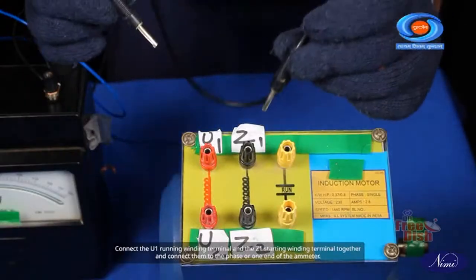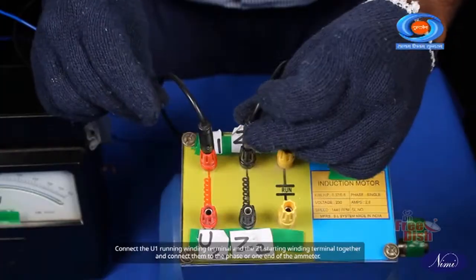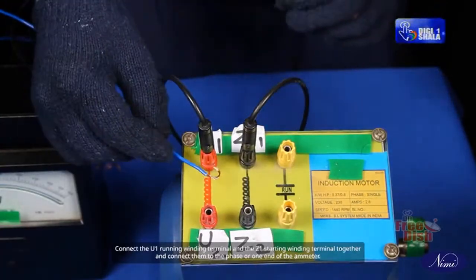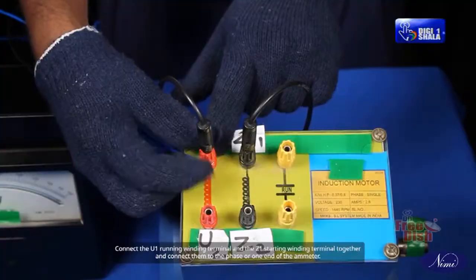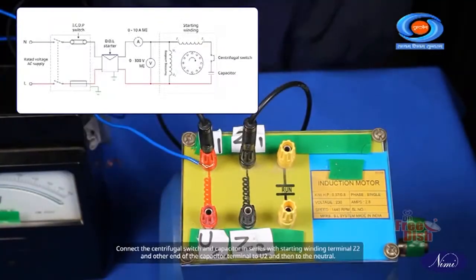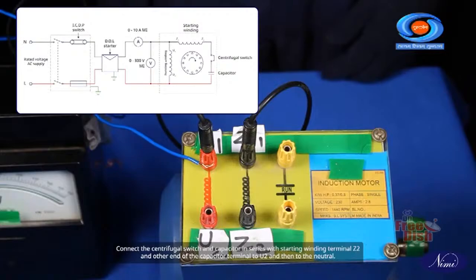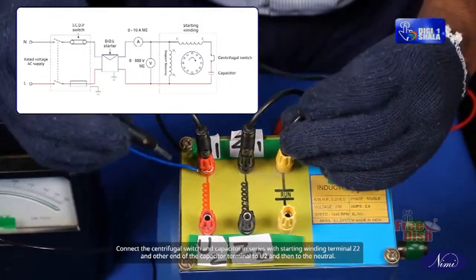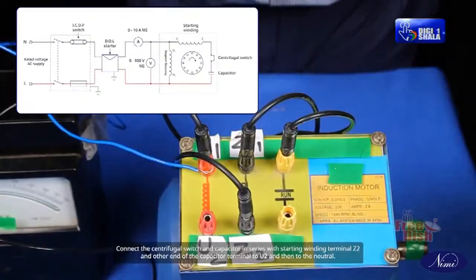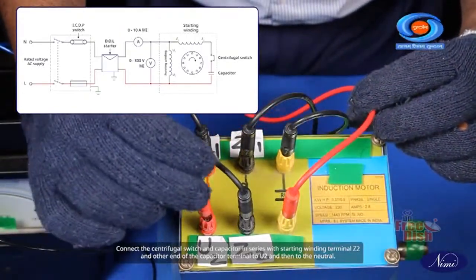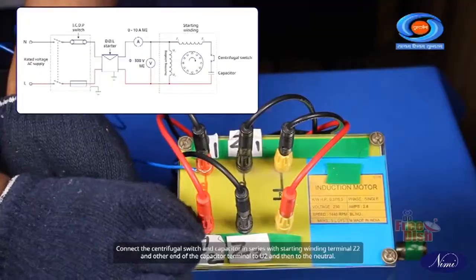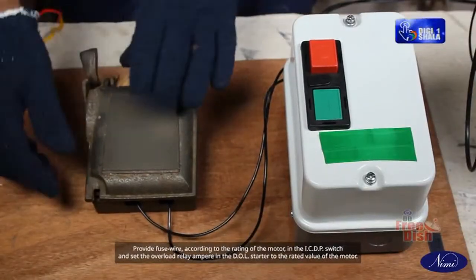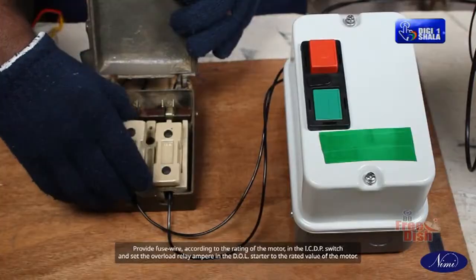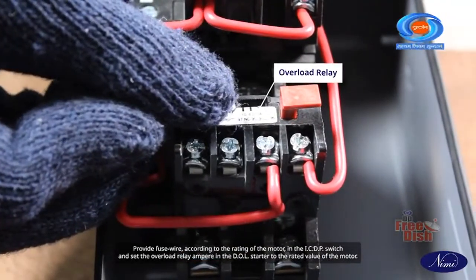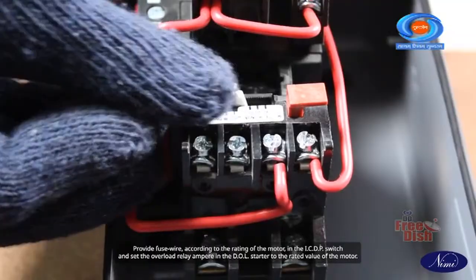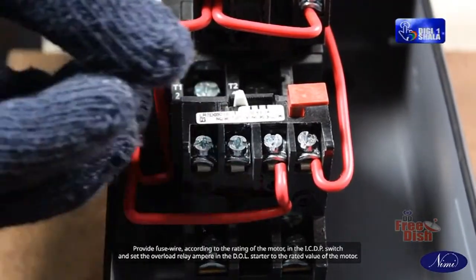Connect the U1 running winding terminal and the Z1 starting winding terminal together and connect them to the phase or one end of the ammeter. Connect the centrifugal switch and capacitor in series with starting winding terminal Z2, and the other end of the capacitor terminal to U2 and then to the neutral. Provide fuse wire according to the rating of the motor in the ICDP switch and set the overload relay ampere in the DOL starter to the rated value of the motor.